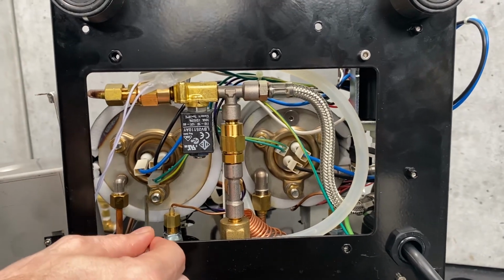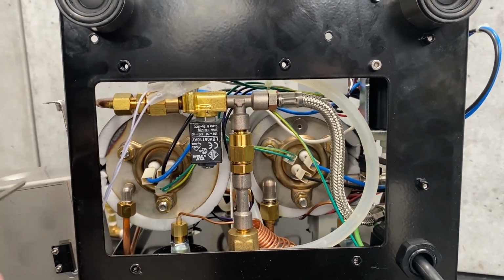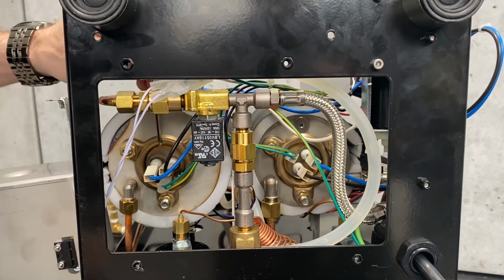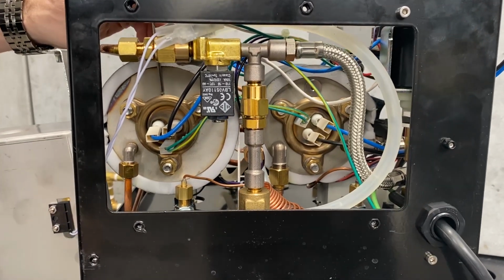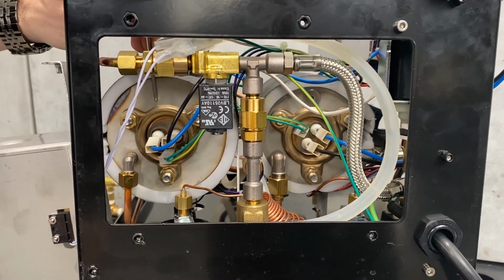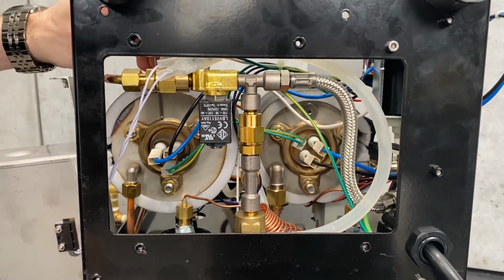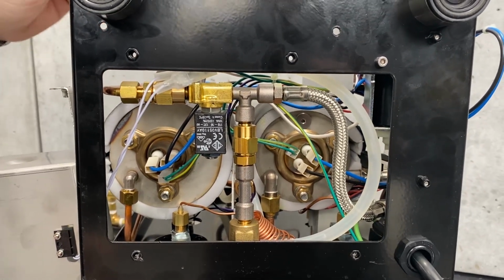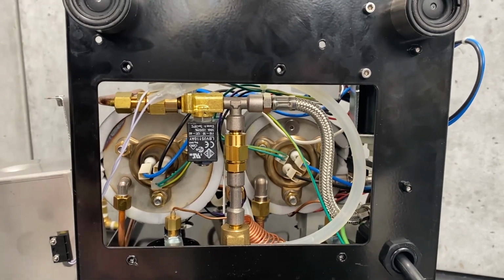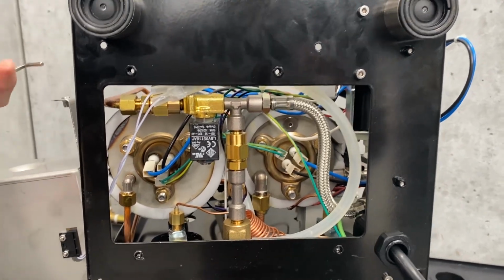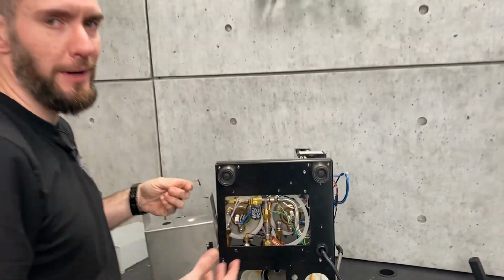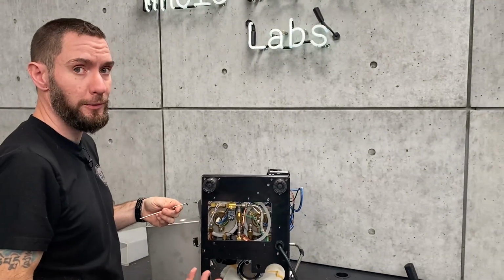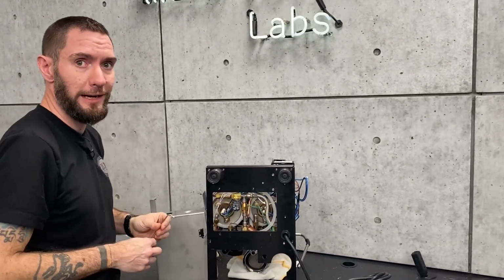If you ever do take these out to inspect your boiler, keep in mind there is a silicone gasket between the element and the boiler. They don't always fare well with being taken off and put back on, so make sure you have a replacement gasket before you do that, just in case it doesn't go back together well.